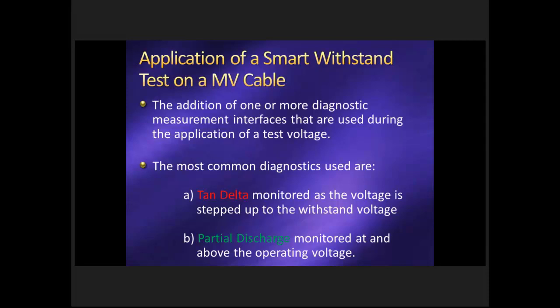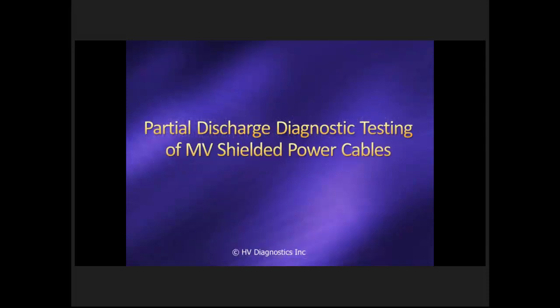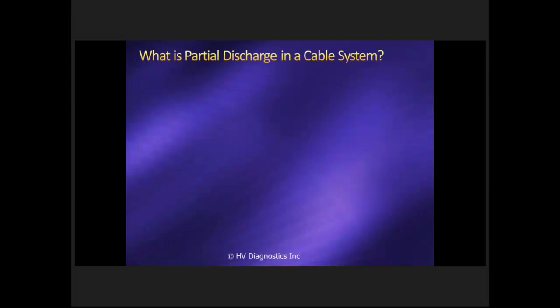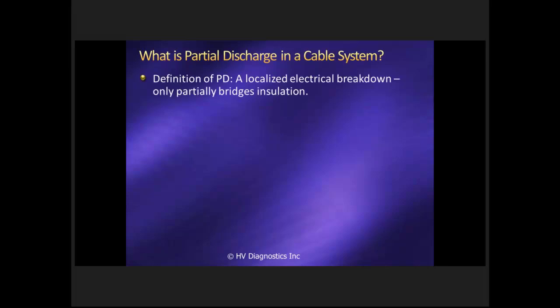Typically, tan delta you apply at half operating voltage and you step it up to the IEEE test voltages, as I showed you in that previous table. With partial discharge, you typically start at operating voltage and you end up at the IEEE test levels in that table as I mentioned earlier. So let's look at partial discharge testing of shielded cables. We know now what type of power supply we need for it. Let's look at the actual diagnostic interface.